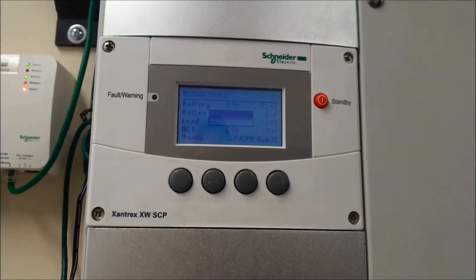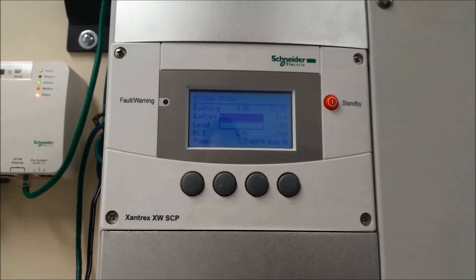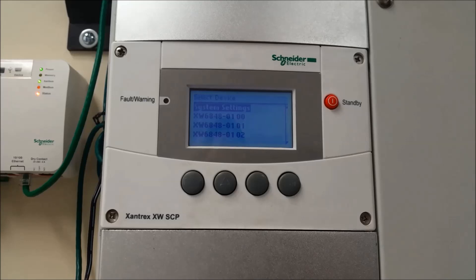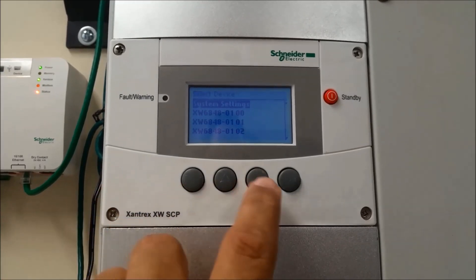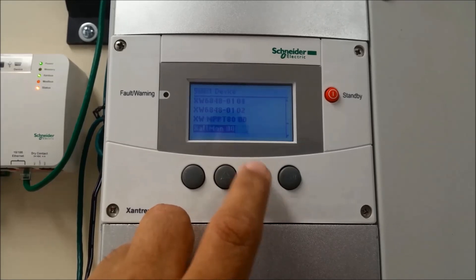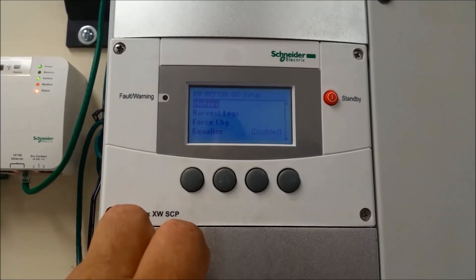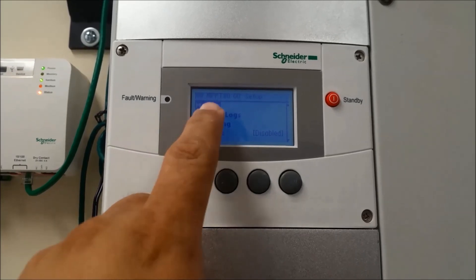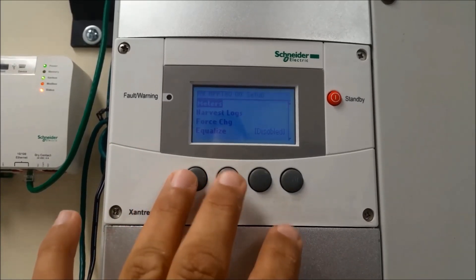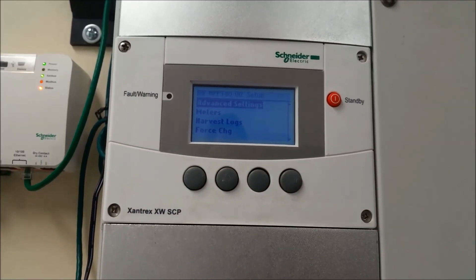Secondly, we're going to go to the advanced settings for the MPPT Solar Charge Controller. Again, we're starting from the home screen. We're going to press enter one time — this brings you to the select device screen. This time, we're going to go a little bit further to highlight the MPPT. We're going to press enter to get to the unit setup screen. From the setup screen, you'll notice meters is highlighted. And again, we're going to press enter, up, and down together to enable the advanced settings.